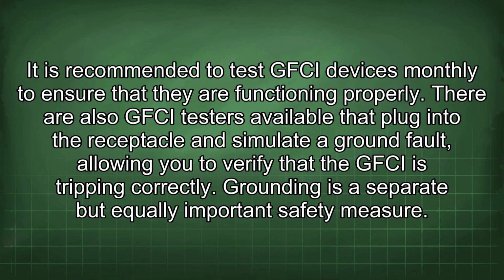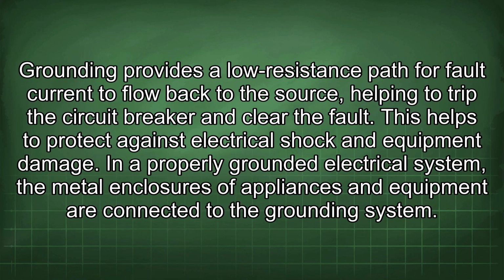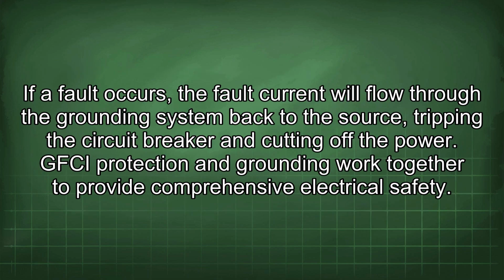Grounding is a separate but equally important safety measure. Grounding provides a low-resistance path for fault current to flow back to the source, helping to trip the circuit breaker and clear the fault. This helps to protect against electrical shock and equipment damage. In a properly grounded electrical system, the metal enclosures of appliances and equipment are connected to the grounding system. If a fault occurs, the fault current will flow through the grounding system back to the source, tripping the circuit breaker and cutting off the power.